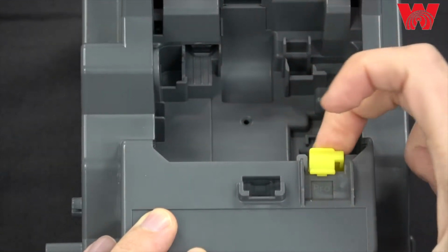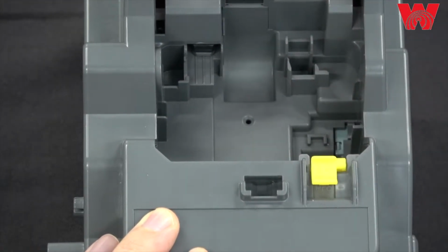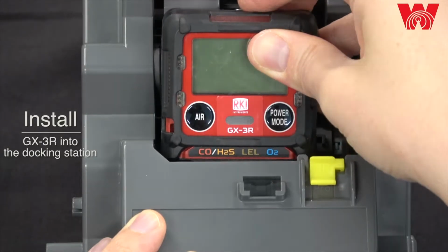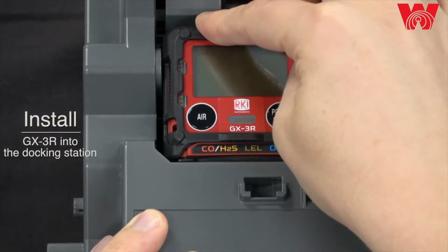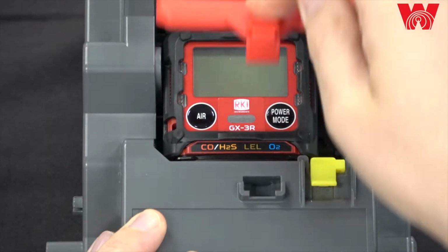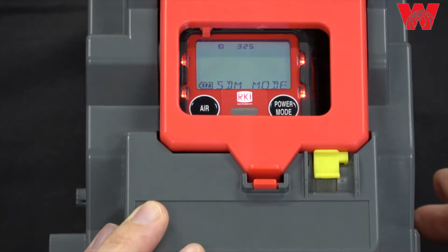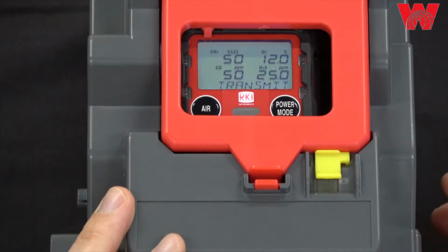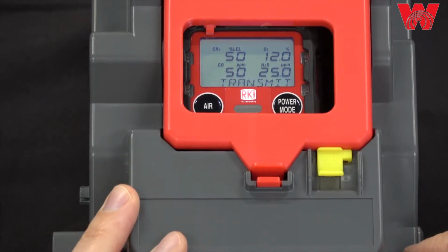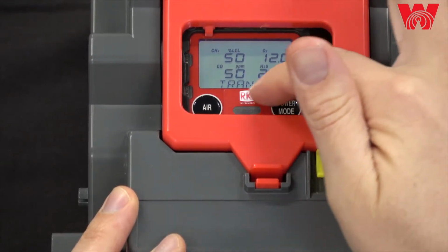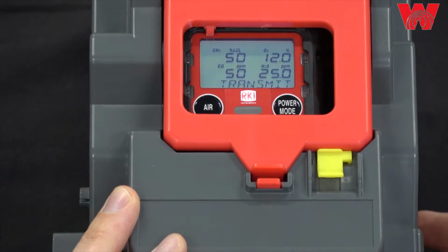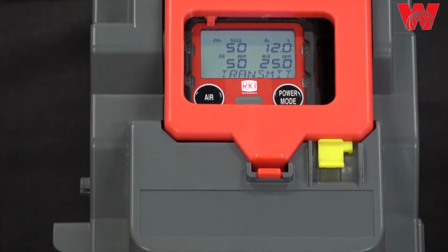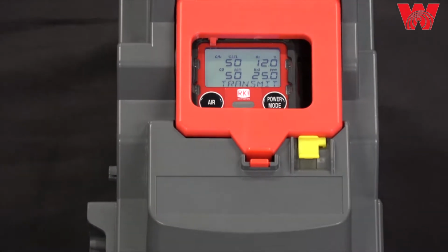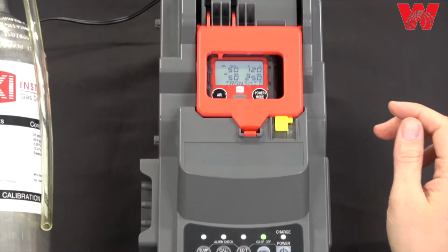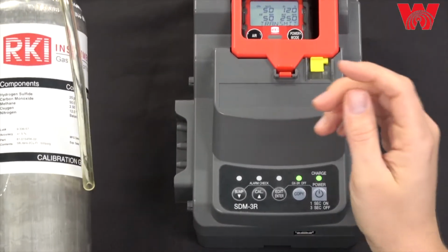So I'm going to put it back up, make sure it clicks all the way into place. Install your GX3R, push all the way down, and close the red lid. The instrument turns on automatically and connects to the SDM-3R. These are the auto calibration values that we're going to be using for our calibration. They need to match the values listed on your calibration cylinder. If they don't match, you need to change the auto cal values in the GX3R.